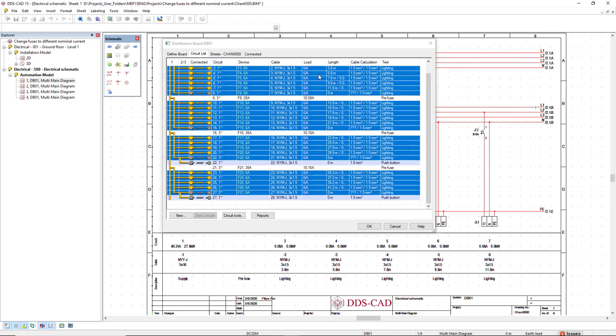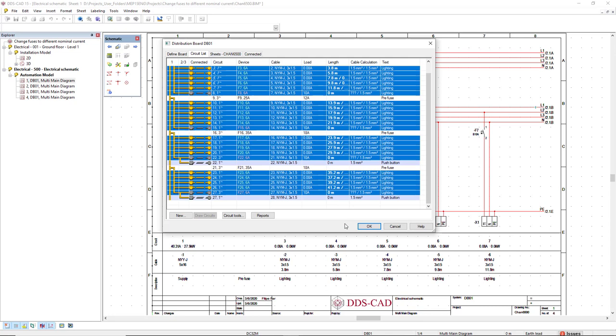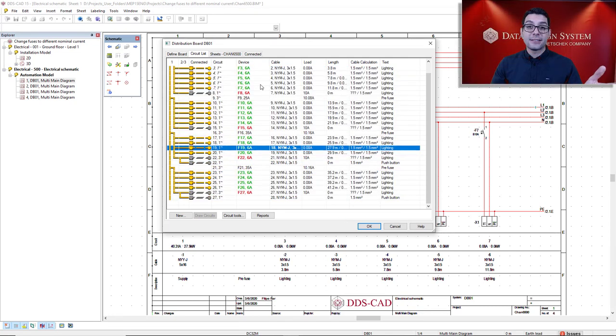Now, move your cursor again to load or length columns, right mouse click and select the option edit. Now, we will reset the IB fixed to IB calculated and click OK.